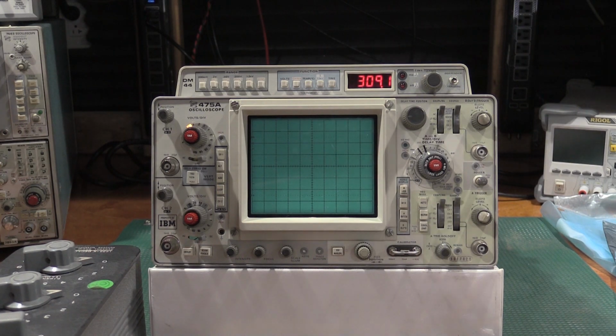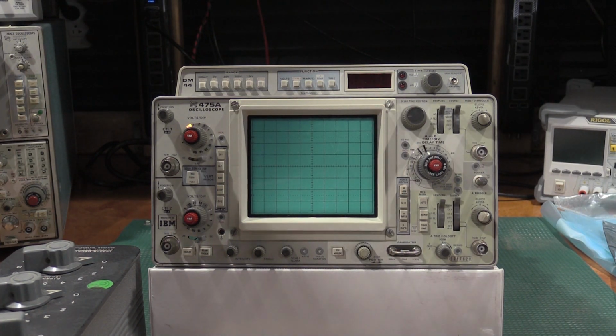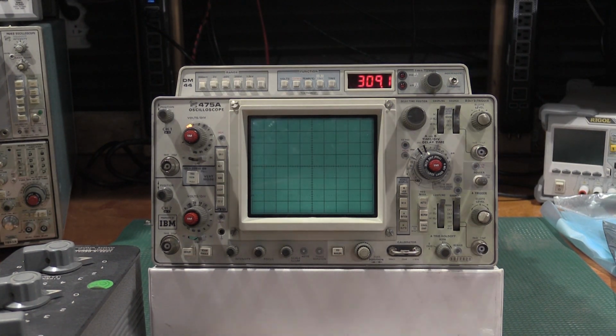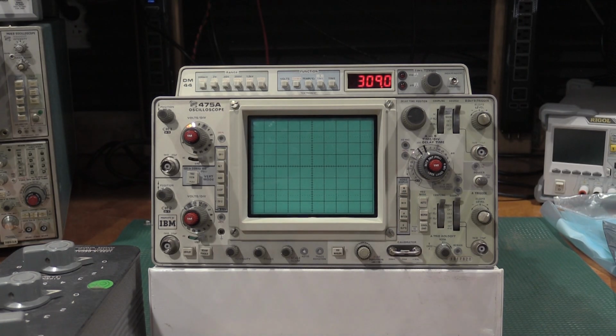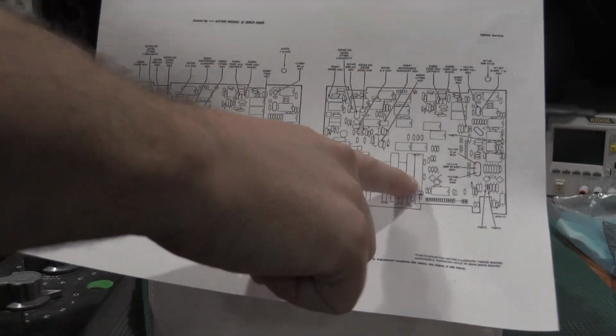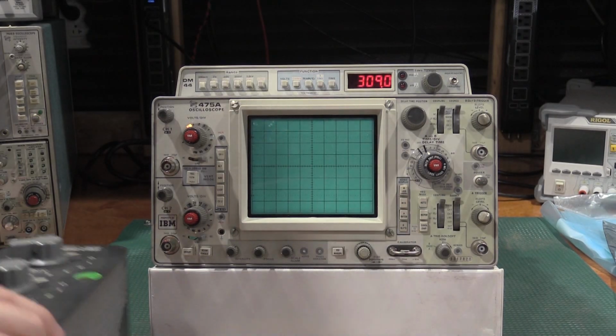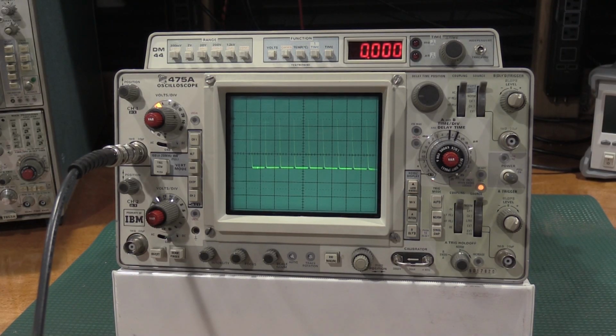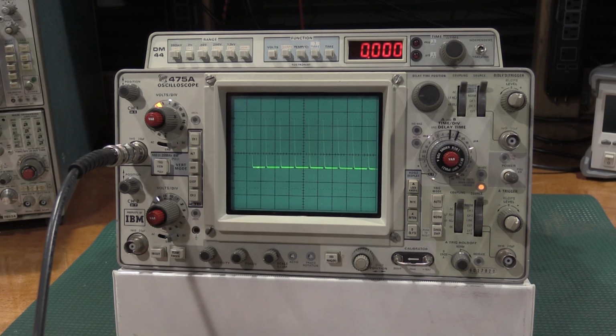So next is the timing section for the scope, and we will need time marks for that. In the DM 44 manual, make sure you're using the correct section of the manual, because there's an alignment procedure for a 465 and 465B, and then there's an alignment procedure for a 475 and 475A. And the adjustment points are different. Perfect example is here. This side is for the 465. This side is for the 475. So, very important.